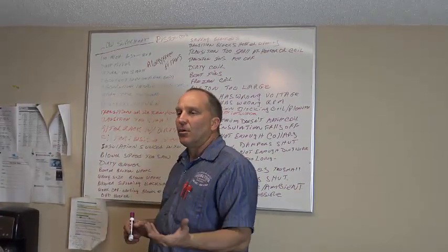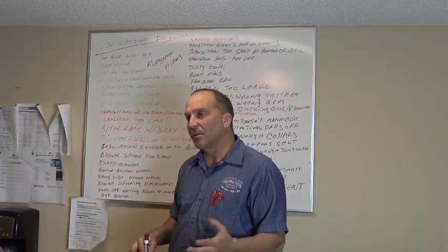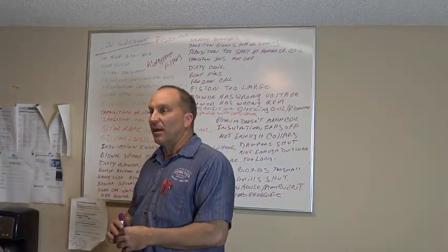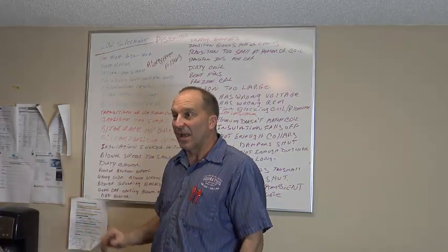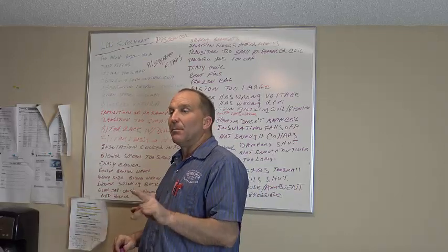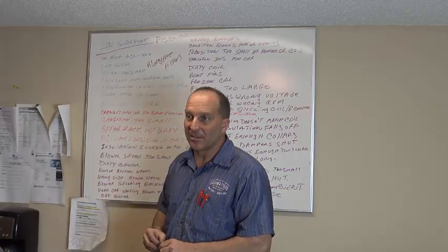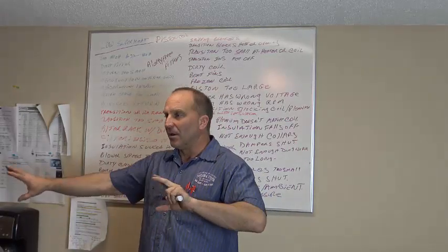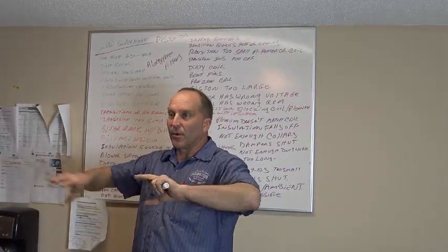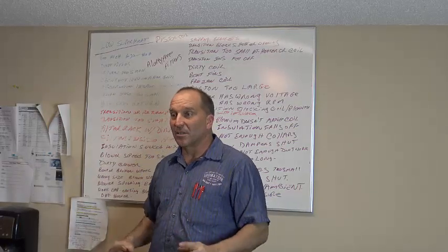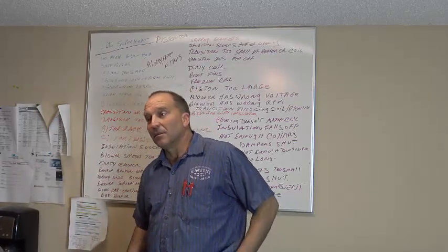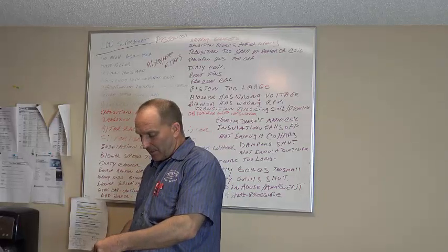Now, if you have what's called the Unico system, the Unico system is a high-pressure duct system. That might run a 3.0 static pressure inside the system. A mobile home unit will run a 3.0 static pressure inside that system. Every duct they run is a 6-inch duct running through it. So if there is a 4-ton system in that trailer, there is 16 ducts running in that system.